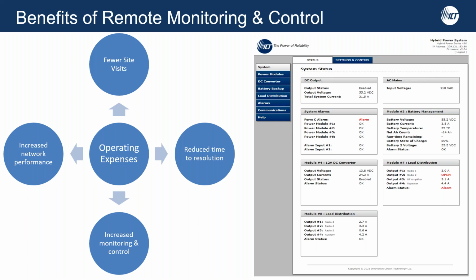Continuing with the benefits of remote monitoring and control: you don't have to go to your site every time something seems wrong. You can remotely log into your system. Our system gives alarms for everything that goes bad at site, whether it's a device not responding or a device restarting. You can log in and check voltage, current, or review a log on the system, download it, and analyze how your loads are behaving. All this leads to fewer truck rolls, fewer site visits, saving time, money, and headaches, and keeps your network resilient all the time.